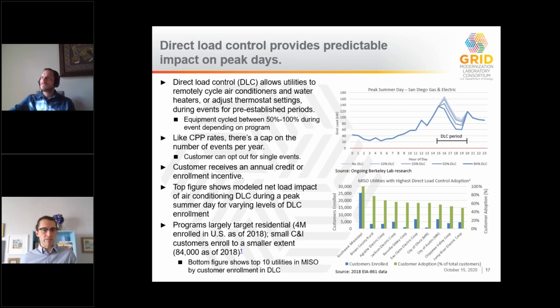During events, equipment is cycled between 50 to 100%, or thermostats are adjusted by a few degrees to cause less HVAC usage. Like CPP, event days are infrequent and customers receive an annual credit for enrollment. The advantage of DLC is that it directly targets equipment responsible for driving peak demand, and by controlling it directly, the utility can better estimate the net load impact. The bottom figure shows the top 10 utilities in MISO with the highest enrollment, as reported by EIA, where many co-ops already have high enrollment of DLC programs.